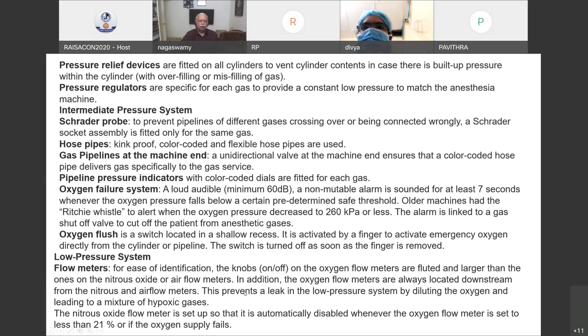And the oxygen flow meter is located downstream to avoid a hypoxic mixture. And the nitrous oxide flow meter is set up so that it is automatically disabled when the oxygen flow meter is set to deliver less than 21%. So this is also called the hypoxic guard, where without opening the oxygen, you cannot deliver nitrous oxide. That is called the hypoxic guard in the flow meter. Then for hypoxia prevention, there is a mandatory minimum oxygen flow in the newer machines. So the question is the newer workstation.